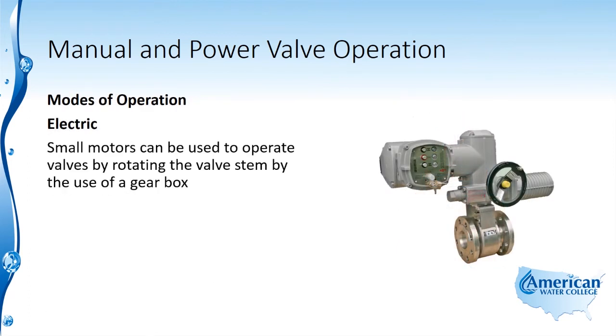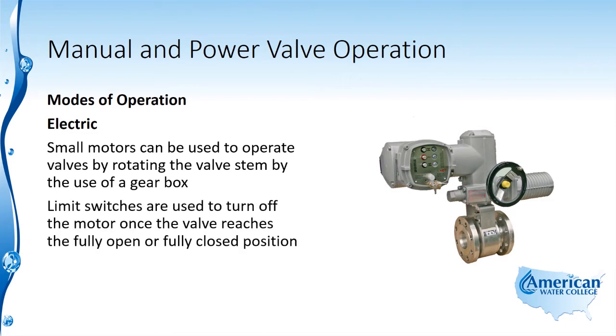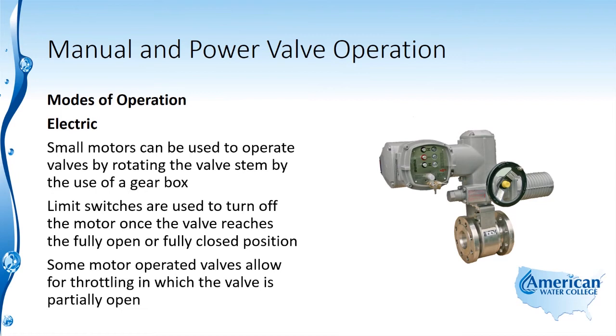Small motors can be used to operate valves by rotating the valve stem by the use of a gearbox. Limit switches are used to turn off the motor once the valve reaches the fully open or fully closed position. Some motor-operated valves allow for throttling, in which the valve is partially open.